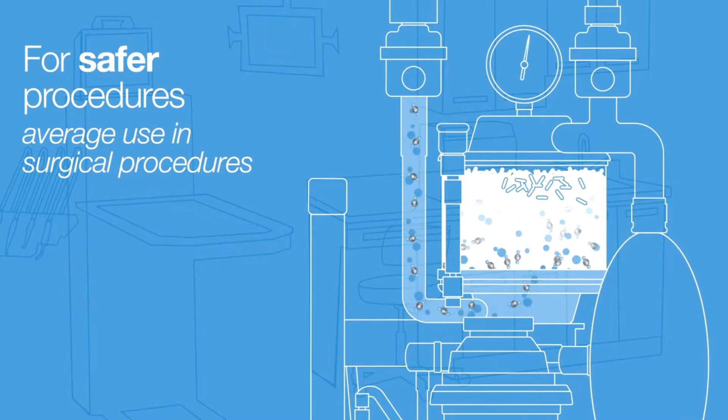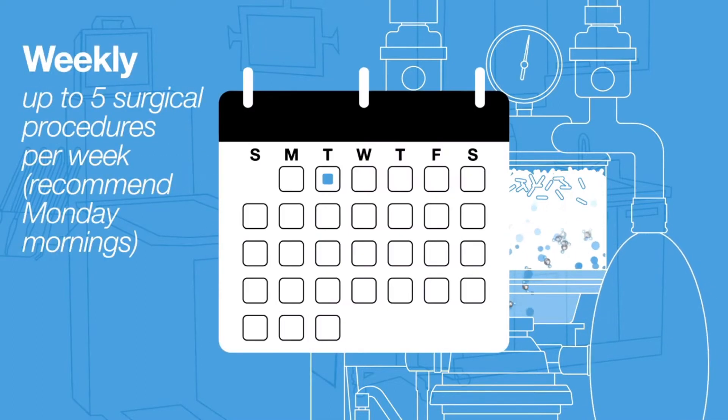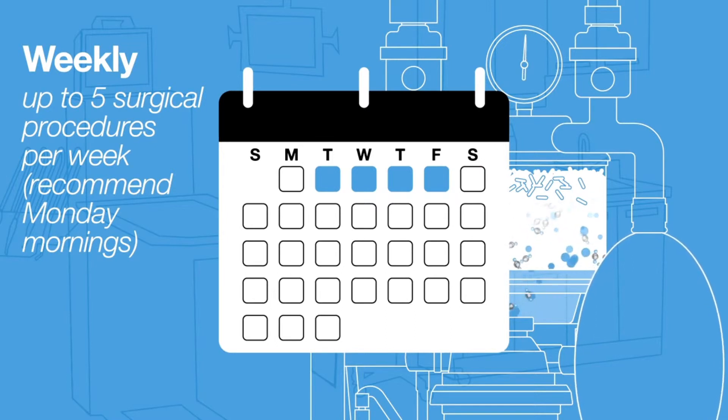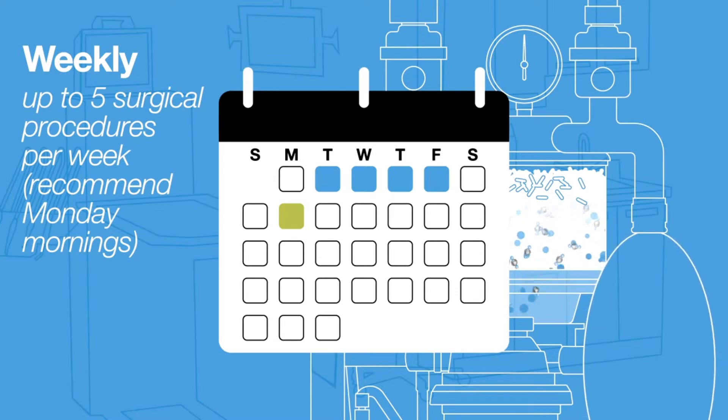For safer procedures, the Soda lime in your anesthesia machine must be replaced regularly based on average use. If you do 5 surgical procedures per week, you should replace the Soda lime weekly. A simple recommendation is to start off each week by changing out your Soda lime.